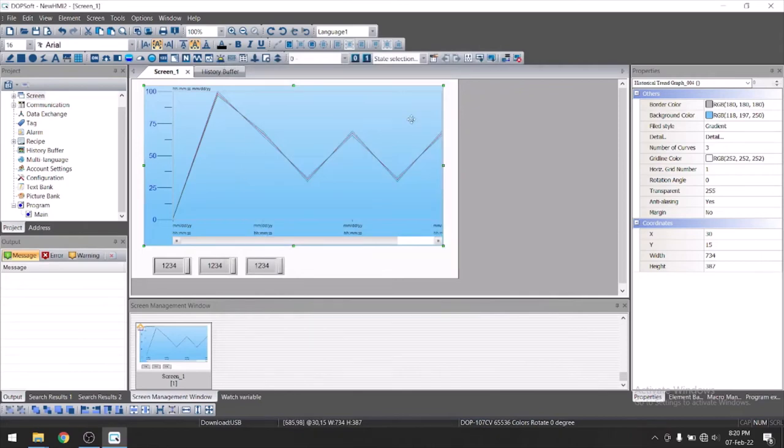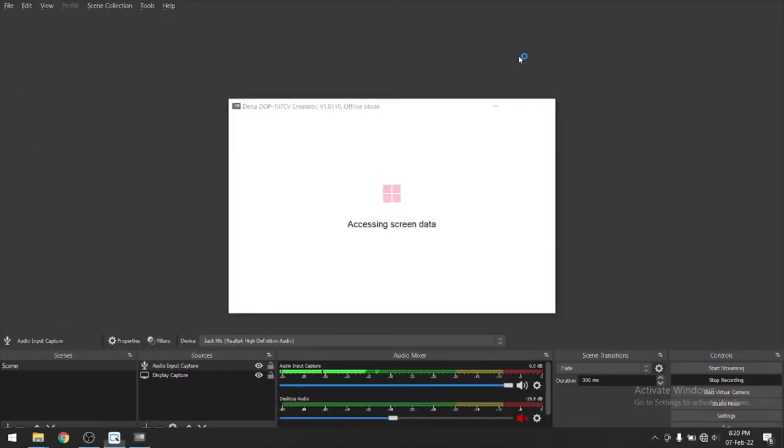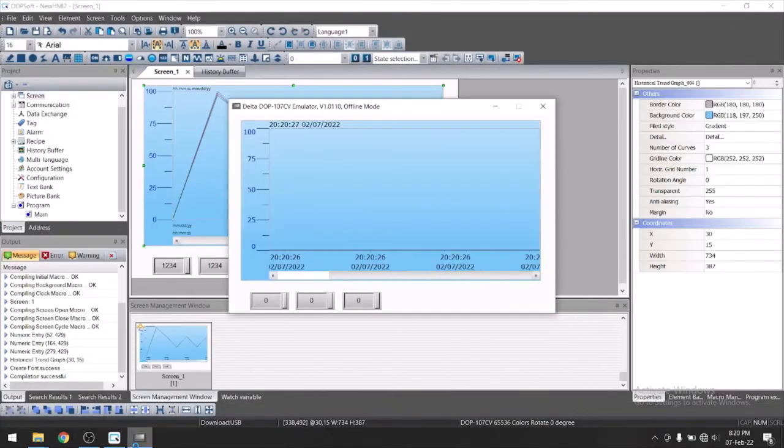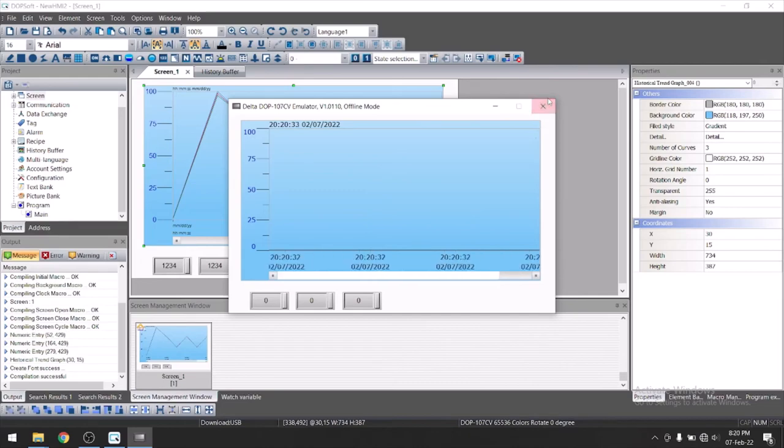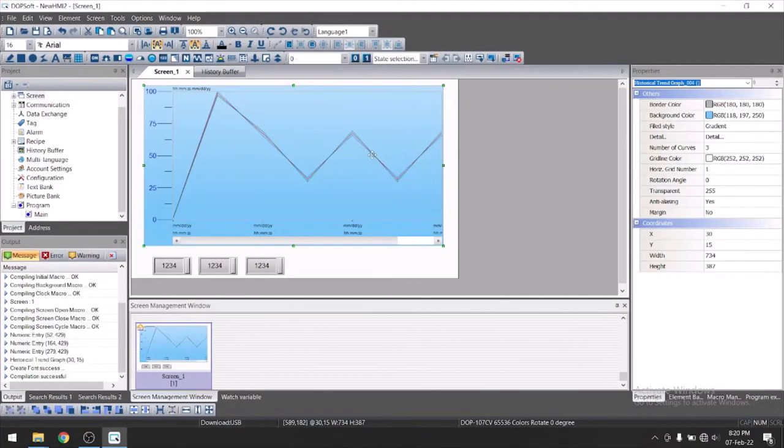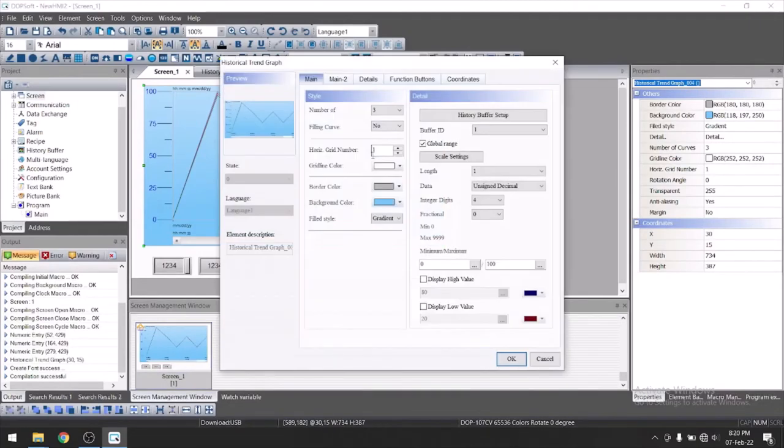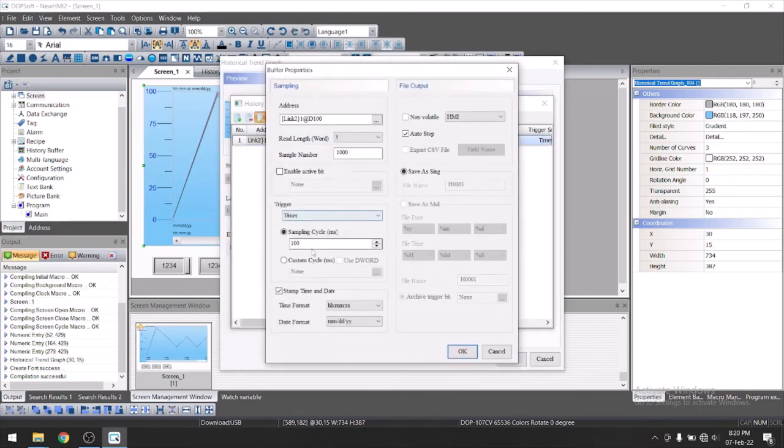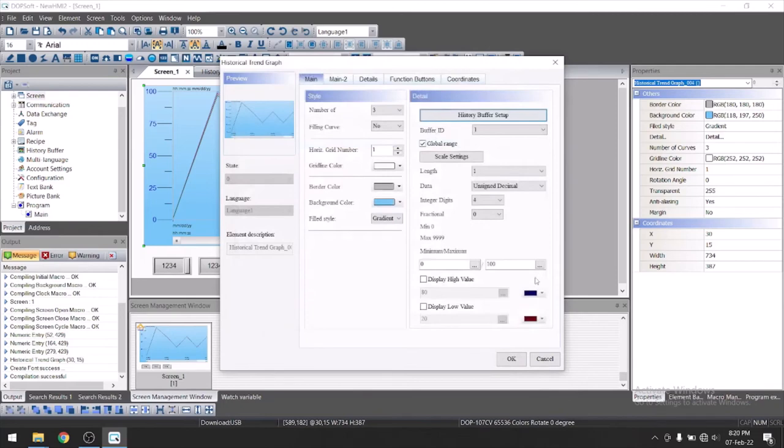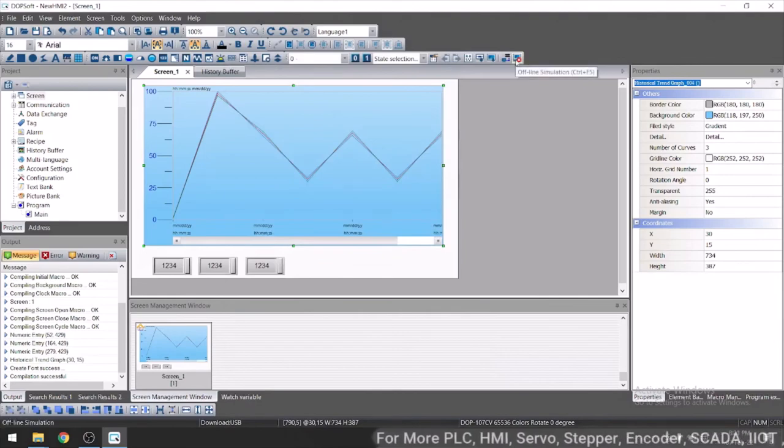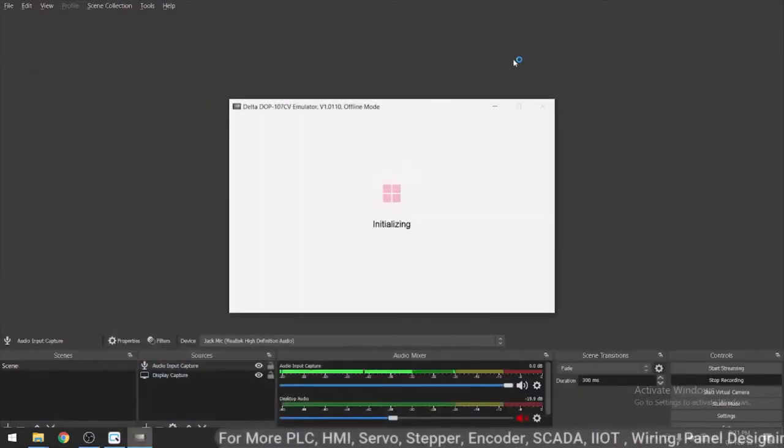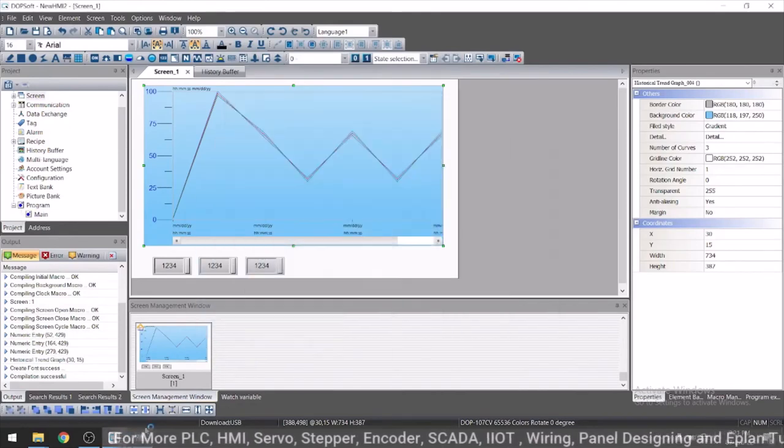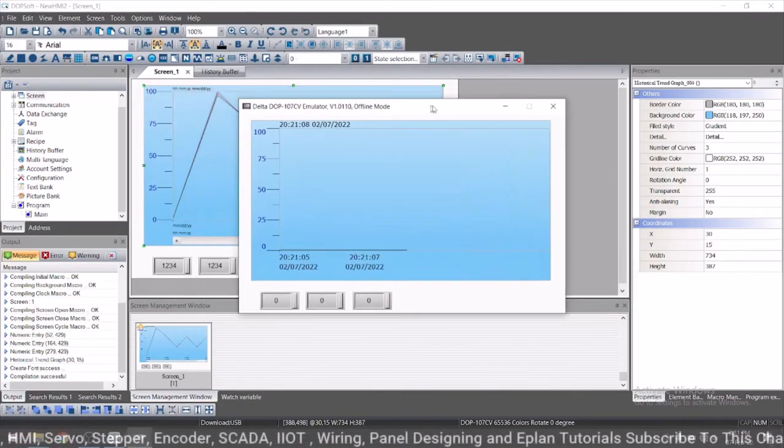Just now let's turn on simulation. It's very fast, so we will minimize the speed. Go to history setup. Edit here. This is sampling cycle, it is now 100 milliseconds. Let's keep it as one second, that is 1000 milliseconds. It means it will collect the data on every second. Now again, let's start the simulation. Simulation started.